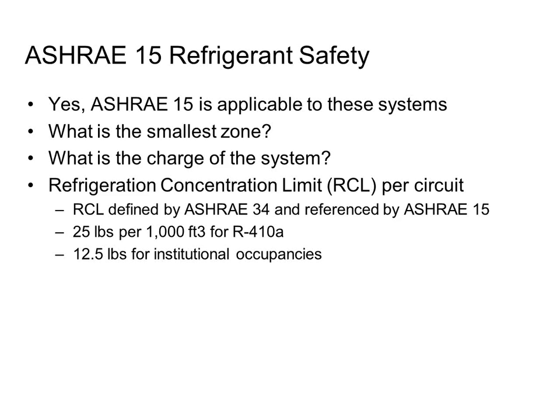If you have an institutional occupancy, your limit gets cut in half. So my 25-pound limit becomes 12.5 pounds. Institutional occupancy has a whole definition, but the summary is, do I have a space where people are not able to evacuate themselves on their own? So nursing homes, hospitals, prisons, these sorts of spaces are institutional. A daycare, you could probably argue, is institutional. Right? If I have these types of spaces, my limit gets cut in half.